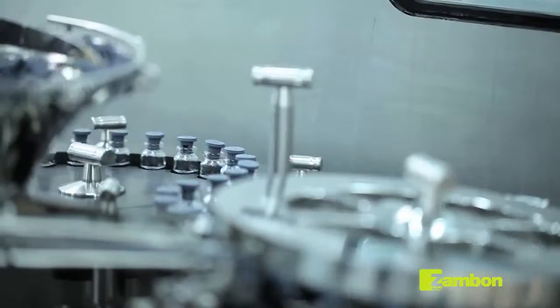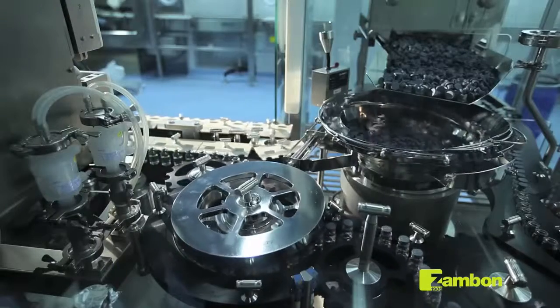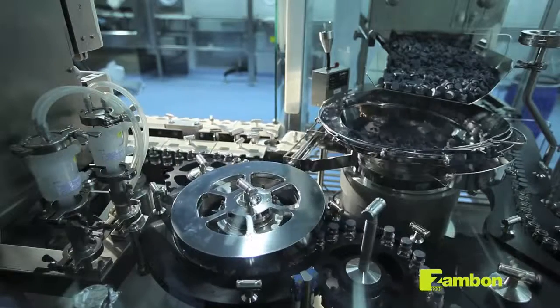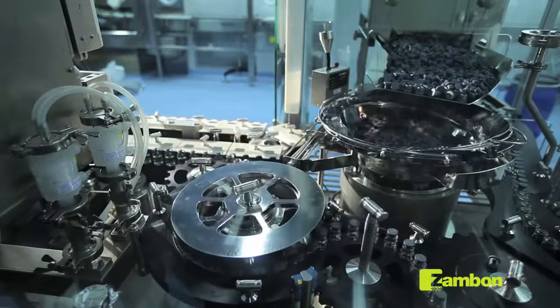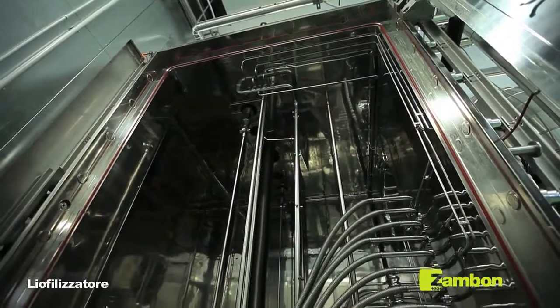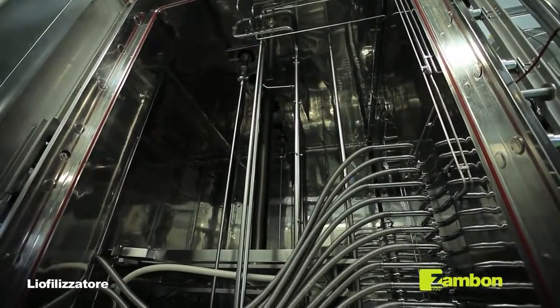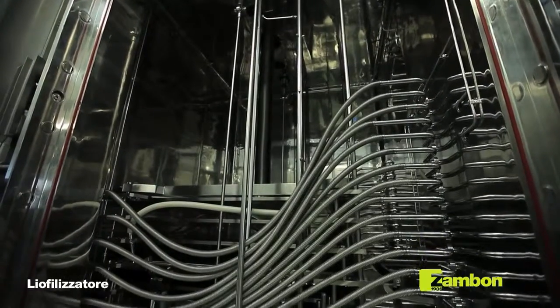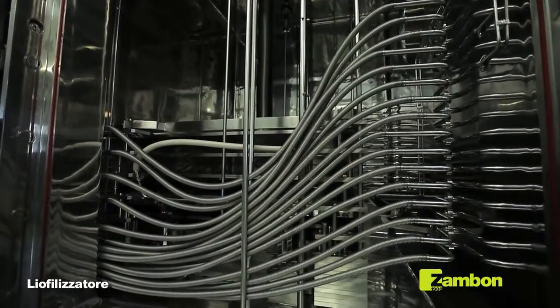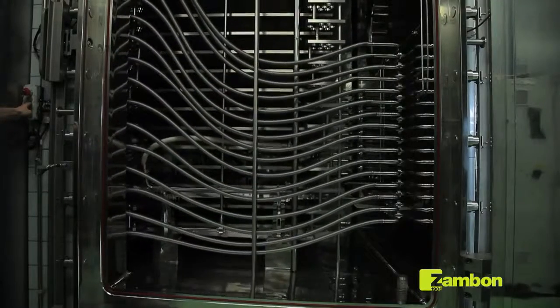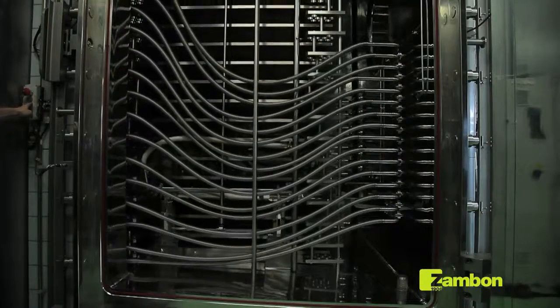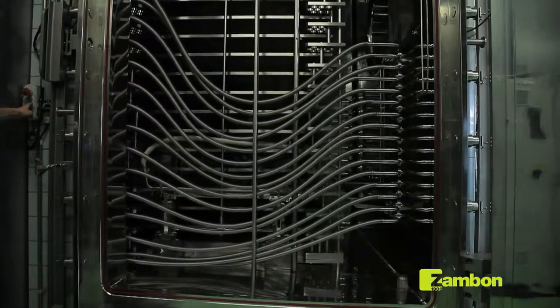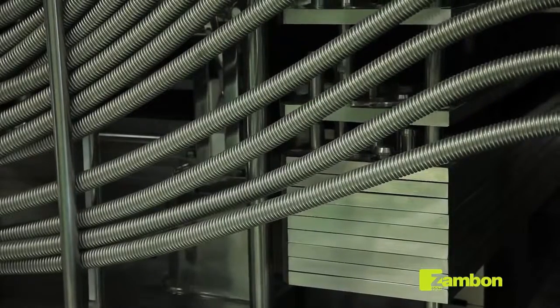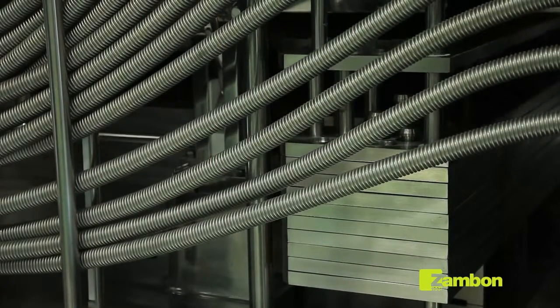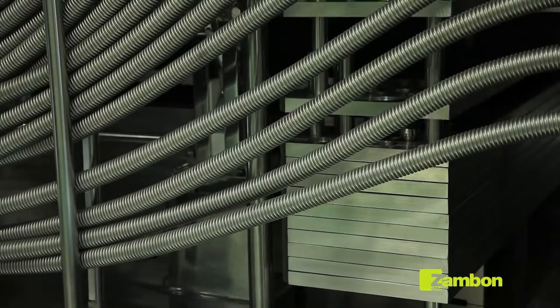The capped bottles are sent to the lyophilizer through an automatic loading system, protected by a continuous flow of sterile air to avoid microbiological contamination. The automatic loading system positions the bottles on the shelf of the lyophilizer. Having completed the loading of a shelf inside the lyophilizer, the shelf itself is raised upwards, and an empty shelf is presented, ready for automatic loading. Once the lyophilizer is loaded and closed, we are able to start the lyophilization process.